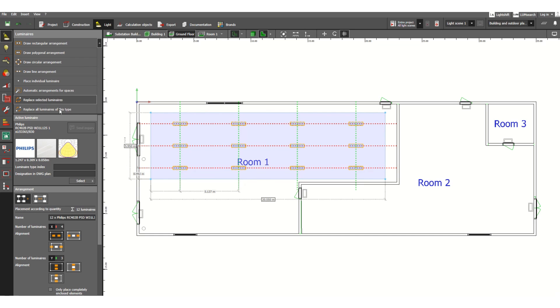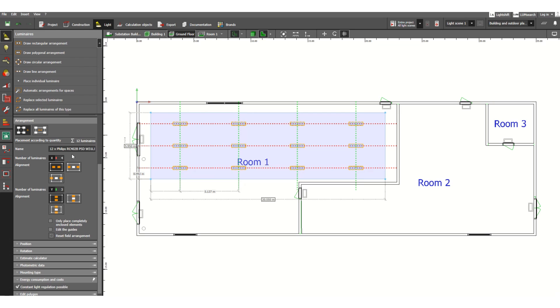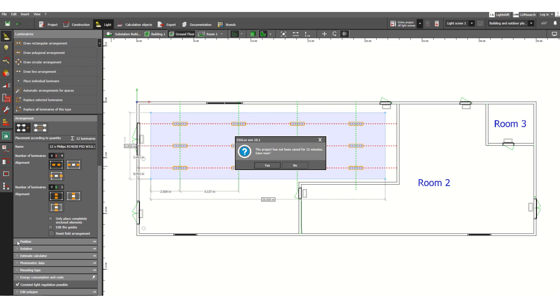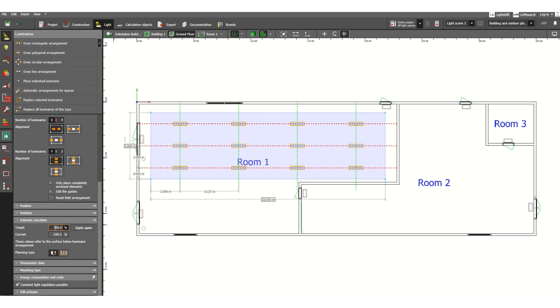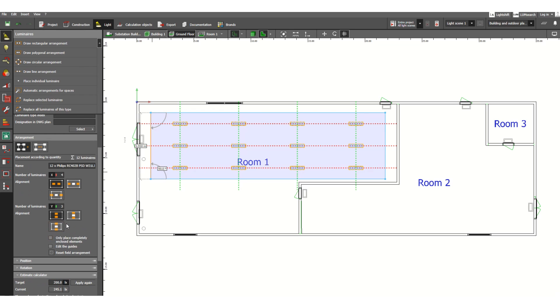Click the second point and move the cursor, then click to complete. DIALux Evo will calculate the number of luminaires — for example, 4 in the X direction and 3 in the Y direction, giving 12 fixtures total. In the Estimate Calculator, the target was 200 lux and the current calculated value is 245.1 lux, which exceeds the requirement — so this is fine.